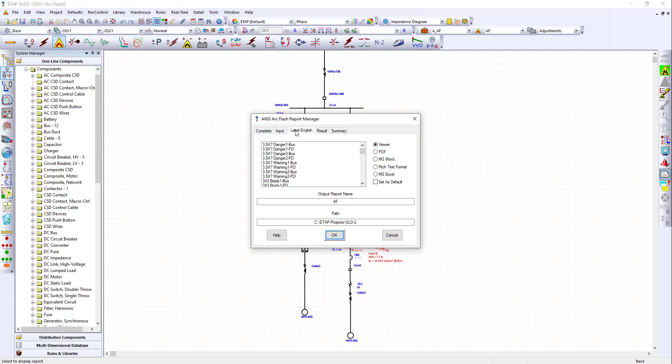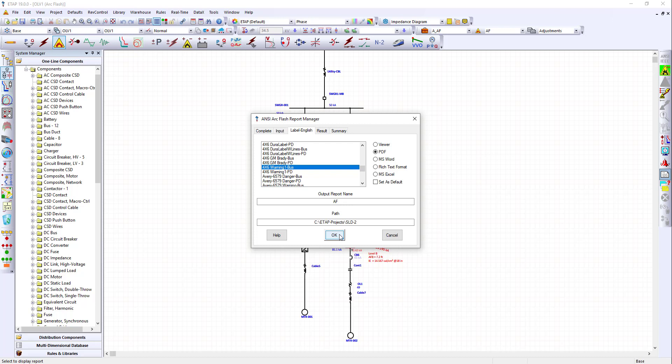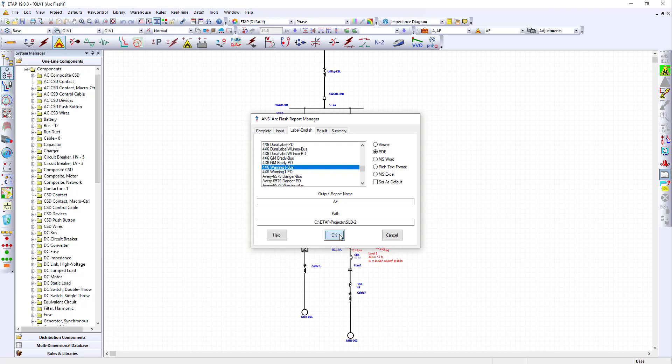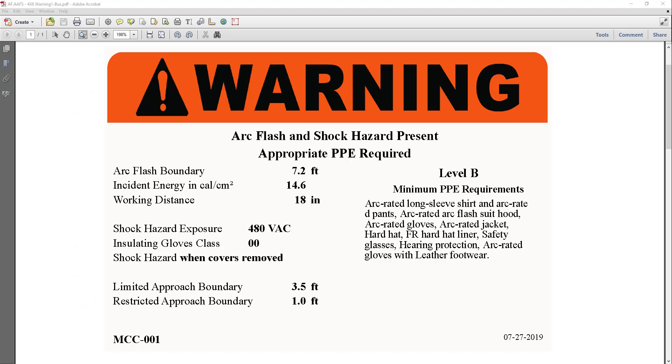To get the Arc Flash labels, click on the Report Manager and then select the Label English tab. We will do PDF labels, so select the PDF option. Next, we need to select a typical label. I will choose the 4x6 Warning1-Bus. Click OK. And there you go. You've just created your first Arc Flash labels.